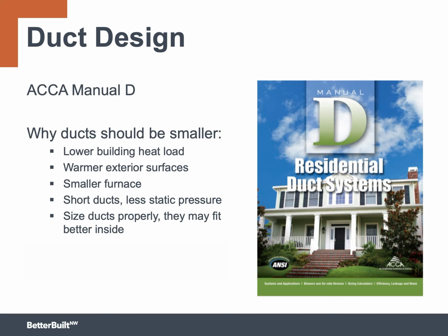Ducts in residential buildings are seldom designed. In a house with the ducts inside, the duct system should be smaller because of the lower building heat load, due to the warmer exterior surfaces from additional insulation and air sealing in the structure itself. Also, there's a smaller furnace, and shorter ducts create less static pressure, so there's less resistance in the duct system. Properly sized ducts also may fit better inside the conditioned envelope. If the system has AC installed or is AC ready, then you should size the ducts to the cooling load and not the heating load.